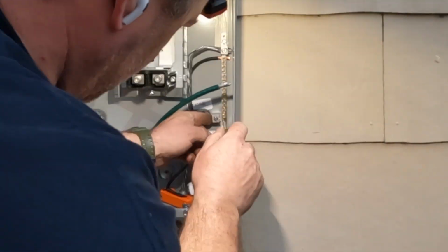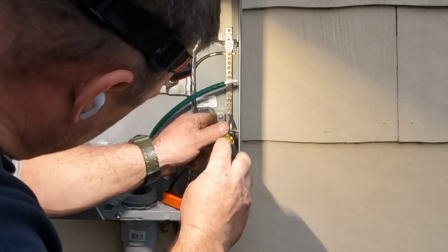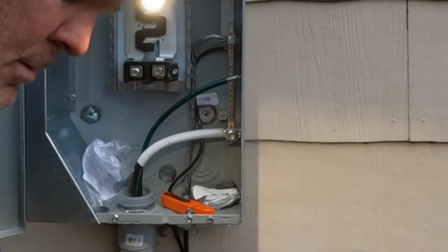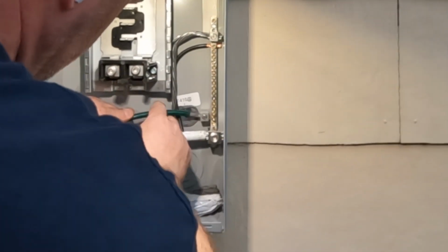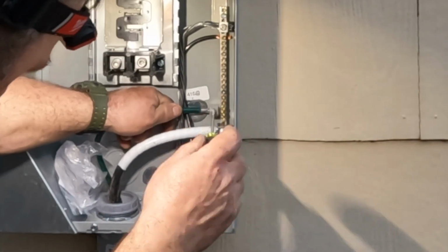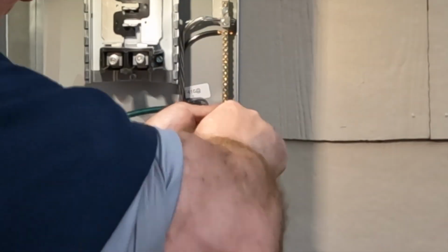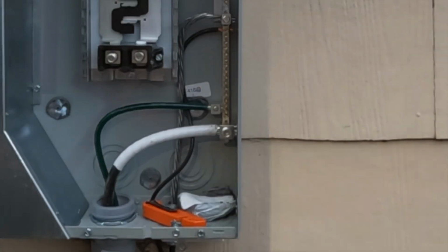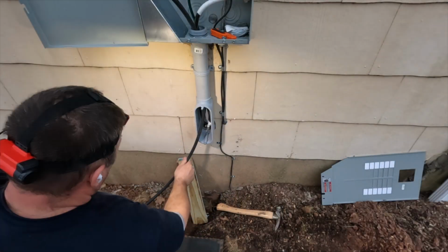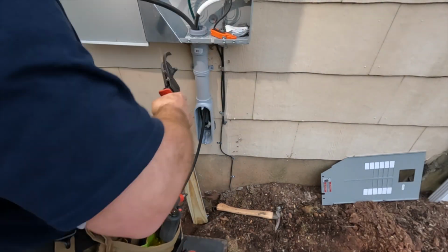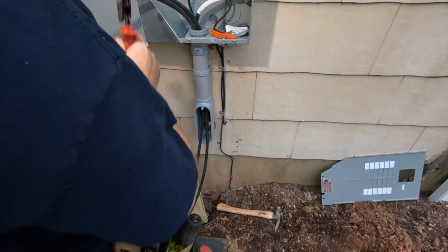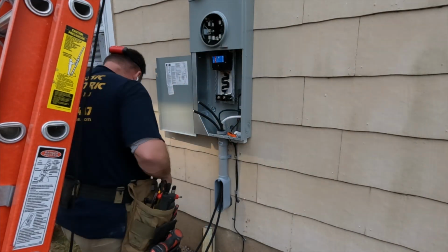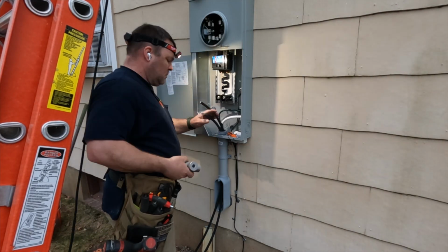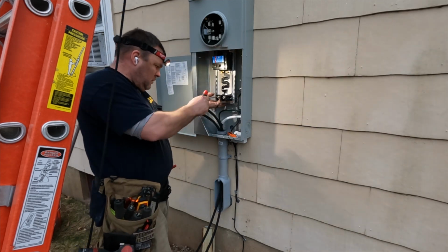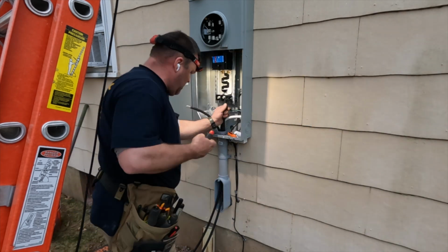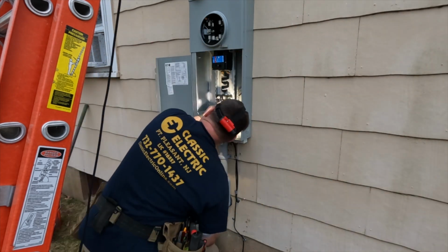And here what I'm doing is I'm putting on this terminal block, because number 2 aluminum is not going to fit in those terminals that come with the ground bar that comes with the enclosure here. So I need to attach this lug to the ground bar, as you see there. And that's where the equipment grounding conductor is derived from. Now, truth be told, this took a lot longer than I thought it would. Folding over the 4/0 aluminum through the LB and down into the panel down below.